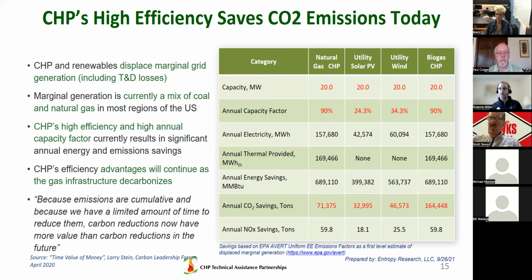One of the other aspects that's crucial in understanding the CO2 savings of CHP is that it also provides useful thermal energy that would otherwise be generated by an on-site boiler or steam generator. The carbon cost of that thermal energy is already built into the gas being consumed by the CHP system, whereas utility wind or utility solar installations would need an additional gas boiler to provide that same amount of thermal energy, thus increasing their carbon a little bit.